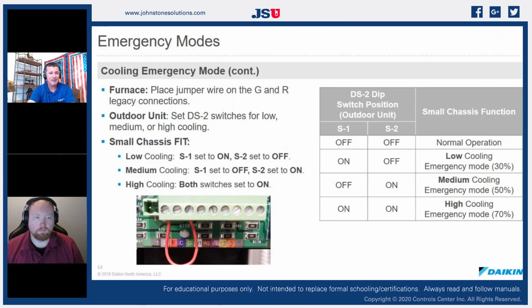A lot of these things even have emergency modes. So as a technician, if we're working on this and we can't quite figure it out, we know we got a communication error and we're not able to get this thing up and running, but we know it's in the communication cables, rip them out. The important part is to get the homeowner comfortable, right? Get rid of the control wires. Put the things into emergency cooling. A lot of these units have emergency cooling. They're going to be locked in. With ours, we can lock them in at 30%, 50%, or 70%.